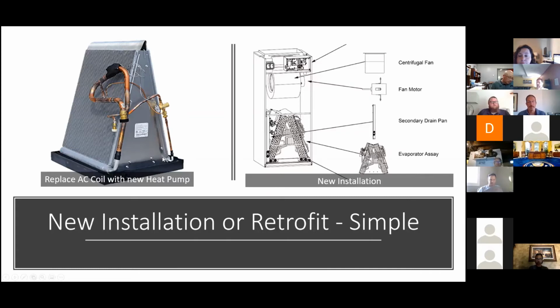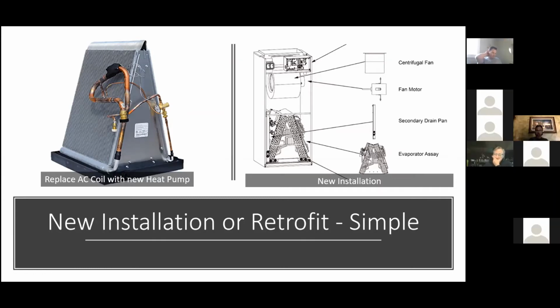If we're replacing air conditioning in a home, we can convert to a heat pump. So we'd pull out the A coil and put in a new one. This one's rated for higher pressure, but it's got a two-way expansion valve. So we're going to be doing heating with the heat pump as much as we can, and then you would have your furnace for backup heat if you didn't have the electric trim heater kit that we use with the indoor unit. All right.